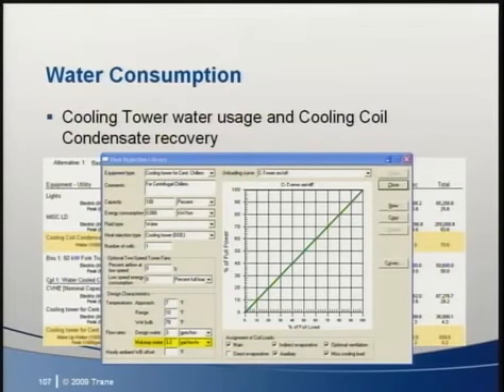Instead, the program uses a cooling tower water usage algorithm, which is based upon cooling tower entering and leaving water temperatures, water flow rates, outside air wet bulb, and the assumed rates of 3% drift and a concentration of 5. We briefly discussed two reasons for water usage in heat rejection equipment. However, a third reason for water consumption is blowdown, as defined by the Marley Cooling Tower Fundamentals. This calculation method is hour by hour and better accounts for the actual makeup water needs.